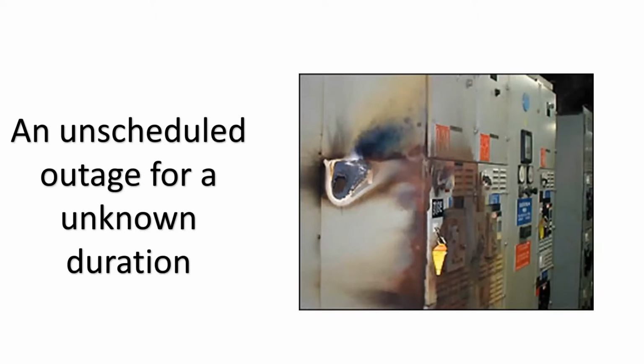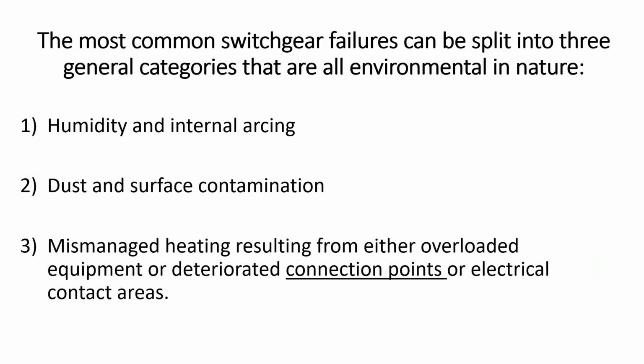Agreed? Okay, next. Here's the 3 most common failures: humidity and internal arcing. We live in Colorado, so humidity isn't a big issue, but with the dry climate, what is the big issue? You can build up static charges, right? Dust, surface contamination—you'll start getting carbon tracking, carbon arcing, and all of a sudden it'll follow that tracking and we'll get a short circuit.